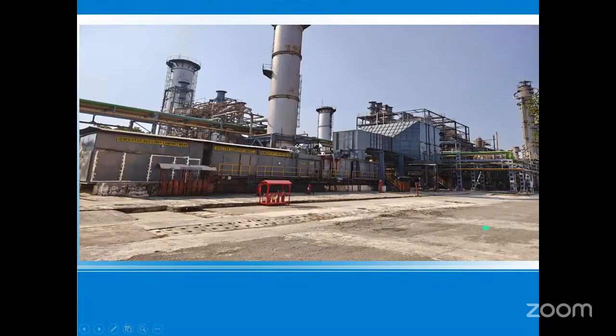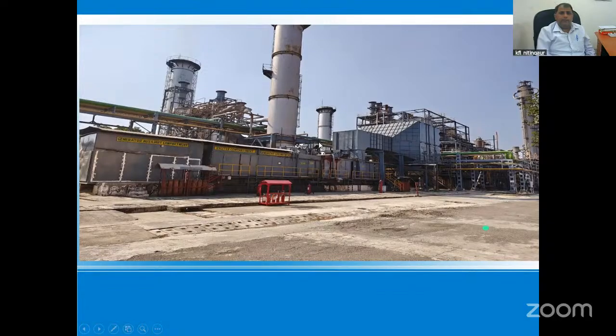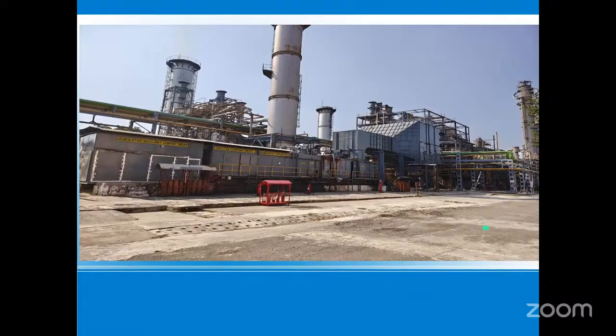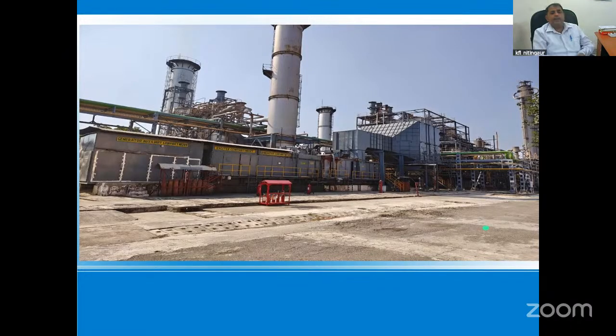For the plant requirement, since the one gas turbine is always in running condition and generates steam approx 80 ton per hour, and our plant requirement is 130 ton per hour, for the rest of the 50 ton per hour, another boiler is used.